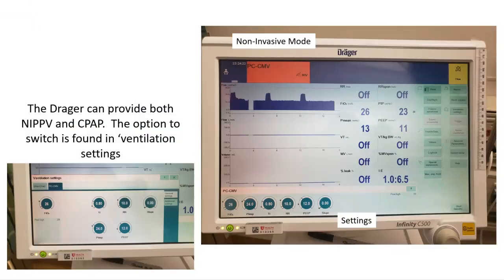So here's the Draeger. We can even use the same circuit. You just take the proximal flow sensor out of line. Put it in a little baggie because maybe we have a kid that might get reintubated. We don't want that flow sensor just flopping around and getting gross and dirty. So put it in a bag, put it where it's safe, because you're not going to need the proximal flow sensor in non-invasive. We can provide both Nippy and CPAP, and this is found in the ventilation settings.